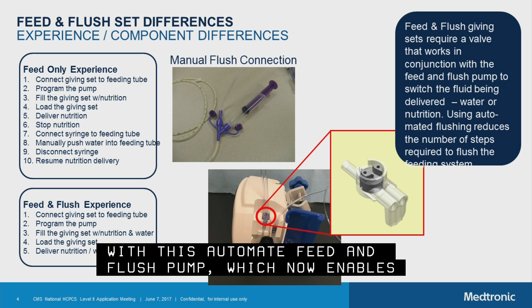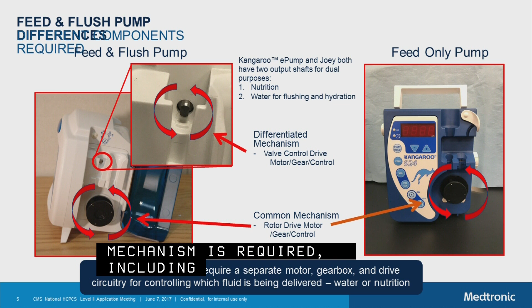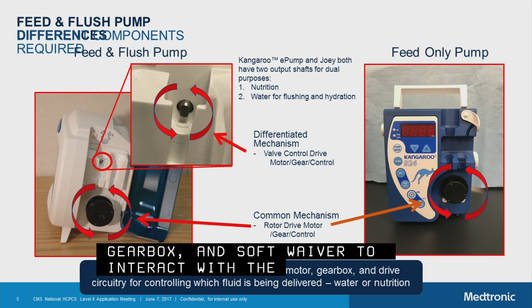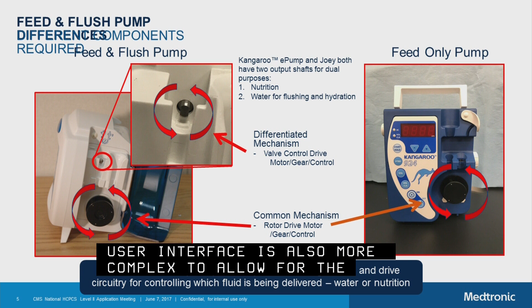To activate the valve in the feed and flush set, a complex mechanism is required, including a gearbox design, which is capable of operating the valve, additional sensors and circuitry to monitor the valve gearbox, and software to interact with the sensors and circuitry to control the infusion. The user interface is also more complex to allow for the automation of not only the nutrition, but also the flushing and hydration volumes, as well as the time interval.